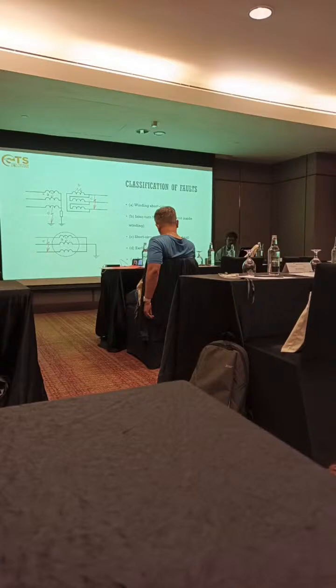tap changer failures. In the case of interturn faults, the interturn fault is in a winding itself. The winding will be insulated with paper, the insulating paper. Between the windings, if the oil absorbs moisture, it will ultimately transmit to the paper. If the paper absorbs the moisture, it leads to a small leakage current between the windings, and that leads to the interturn fault between the windings. That is the one case.